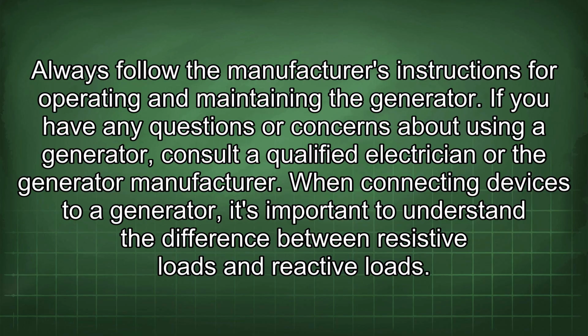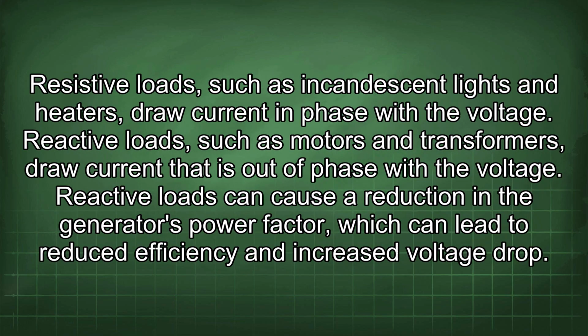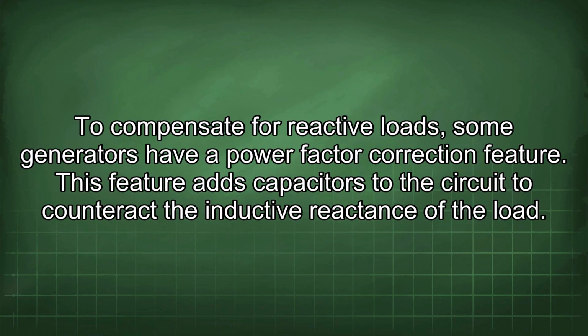When connecting devices to a generator, it's important to understand the difference between resistive loads and reactive loads. Resistive loads, such as incandescent lights and heaters, draw current in phase with the voltage. Reactive loads, such as motors and transformers, draw current that is out of phase with the voltage. Reactive loads can cause a reduction in the generator's power factor, which can lead to reduced efficiency and increased voltage drop. To compensate for reactive loads, some generators have a power factor correction feature.